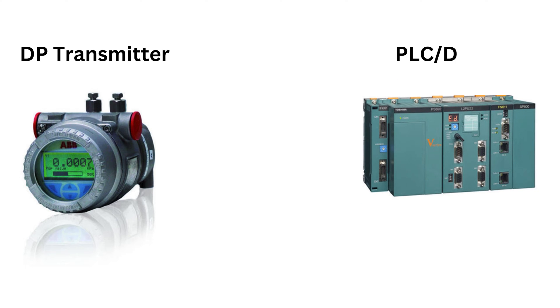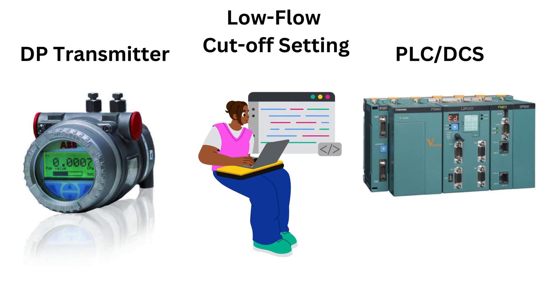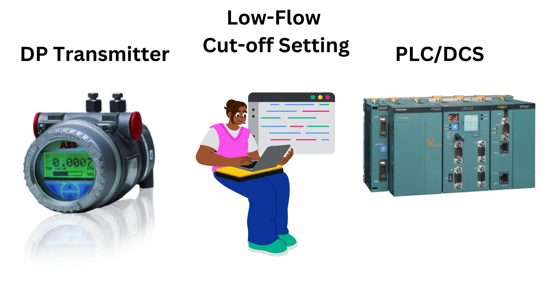If the square rooting is done by the PLC or DCS, then the DP transmitter has a linear output and the low flow cutoff should be programmed in the PLC or DCS.